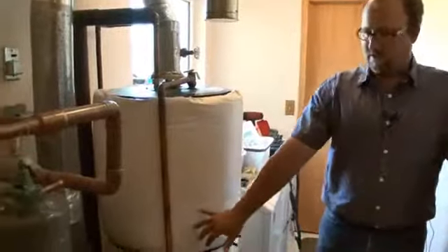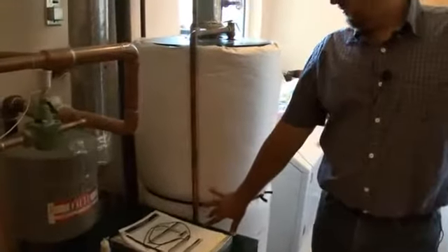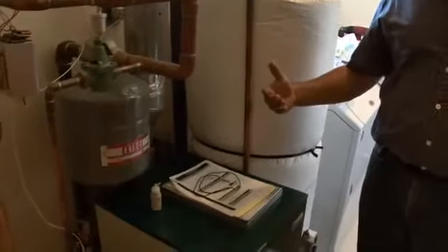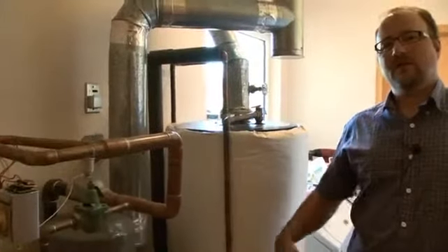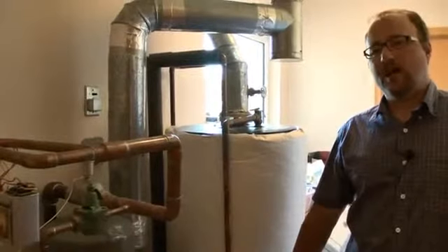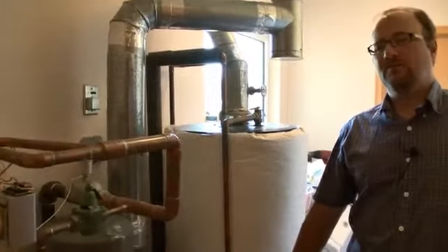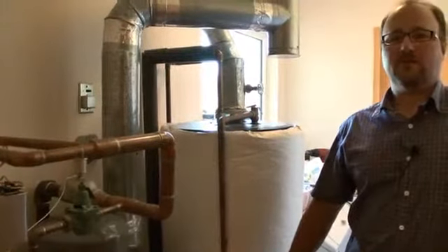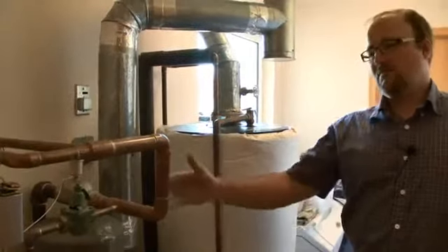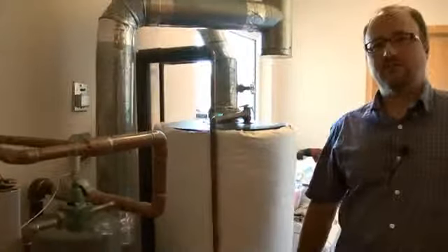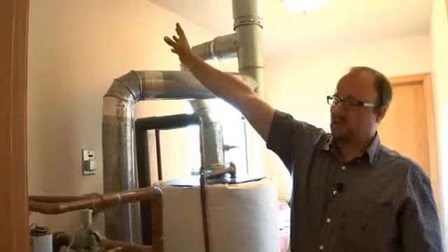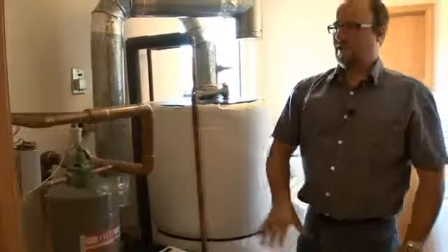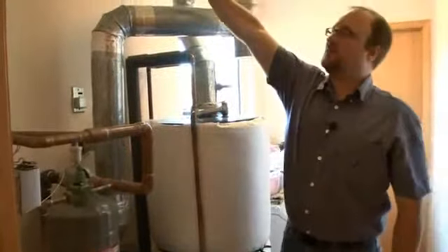So basically we have 120,000 BTUs of fuel gas going in, and we go to the National Fuel Gas Code and it tells us the protocol for how large of openings we need to the outside, or if we're using inside air, how large our openings need to be to get that combustion air to communicate with our appliances. That would be one simple solution, and then abandon this low one, because if you want just one opening, it needs to be within 12 inches of the ceiling.